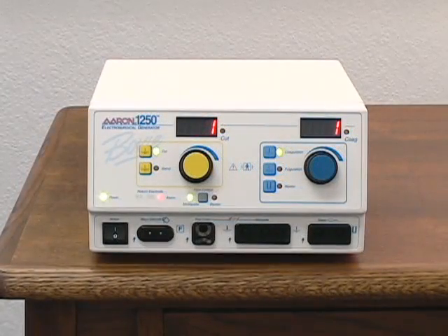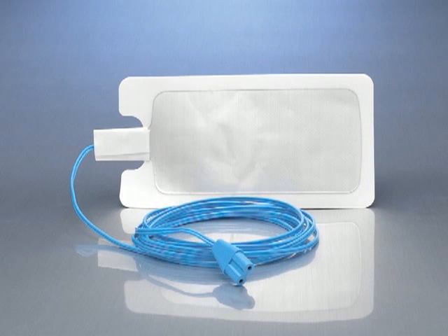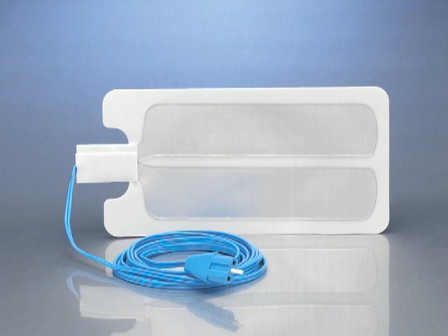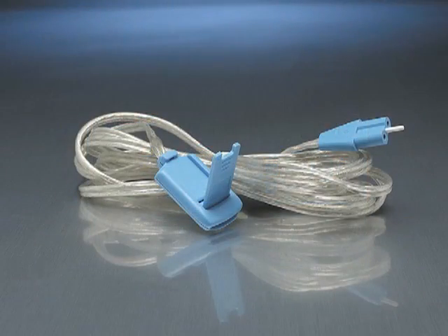The AARON 1250 is an isolated unit and all monopolar modes require the use of a grounding pad. Grounding pads are available in a variety of configurations: solid pad only, solid pad with attached disposable cable, split pad only, and split pad with attached disposable cable. Pads without cables are to be used with the reusable grounding cable.